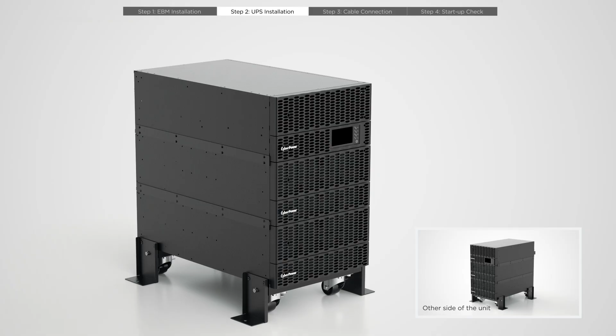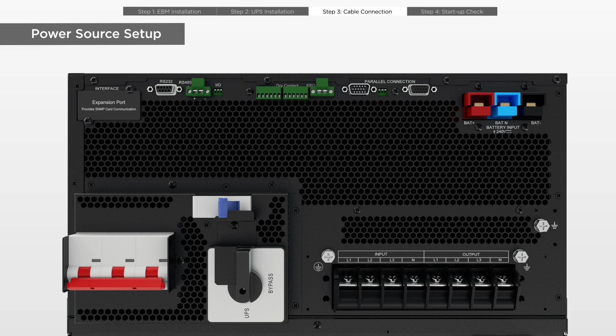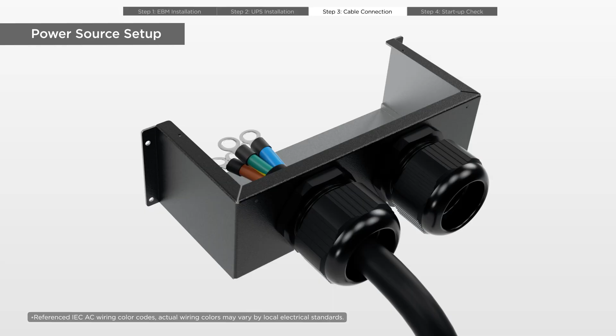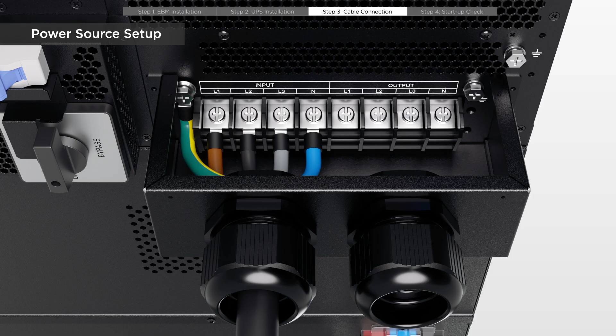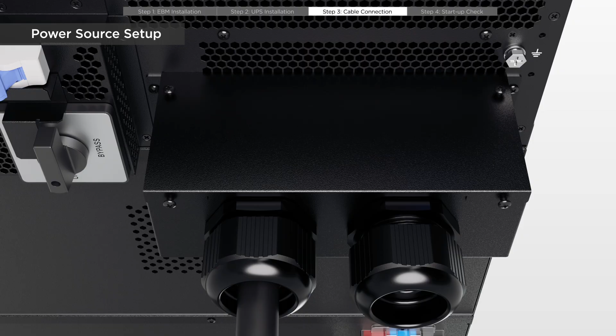Remove the terminal block cover by loosening 4 screws, then loosen and reattach the cable glands. The input circuit breaker must be off before connecting cables. Route the power cable through the cable gland and verify that the phase sequence matches the UPS terminal labeling. Secure the terminal block main box onto the UPS using 4 black truss screws. Tighten the cable gland to secure the power cable. Finally, reinstall the terminal block cover and screws.